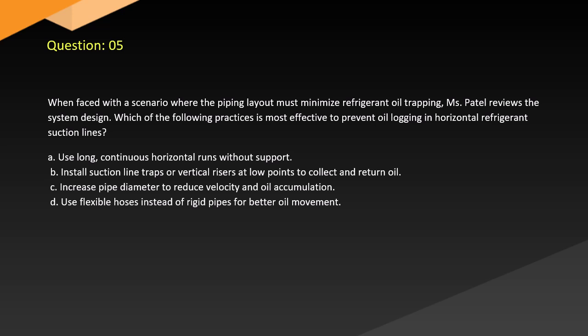Question 5. When faced with a scenario where the piping layout must minimize refrigerant oil trapping, Isa Patel reviews the system design. Which of the following practices is most effective to prevent oil logging in horizontal refrigerant suction lines? A. Use long, continuous horizontal runs without support. B. Install suction line traps or vertical risers at low points to collect and return oil.